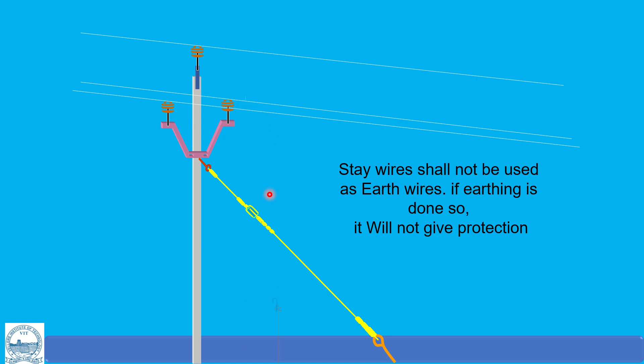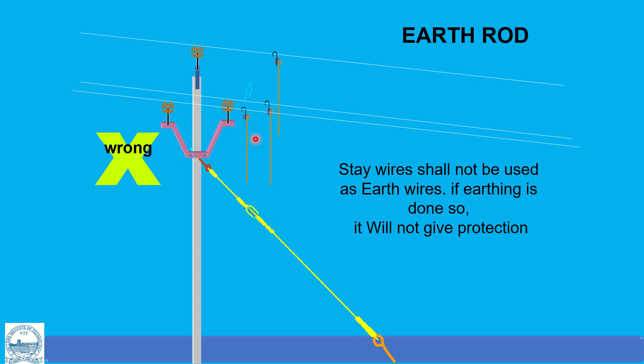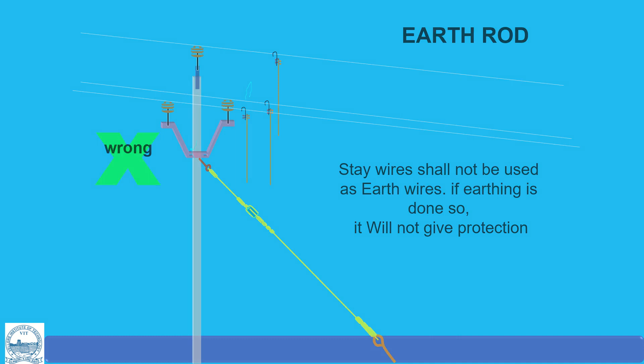So this ensures the person is operating safely. The stay wires shall not be used as earthing wires. These are the common mistakes. In the older days, the poles were supported by means of stay wires. And this is also connected to the ground, but we should not use this as the ground connection or earth connection. We should use a separate ground. Why? Because this is not a perfect conductor like your copper wire. And it is also electrically isolated. Here you can see a porcelain insulator to which the wires are tied. This ensures there are no leakage charges present, and it is always safe for common people, but we should not use this as a ground. This is a wrong method.